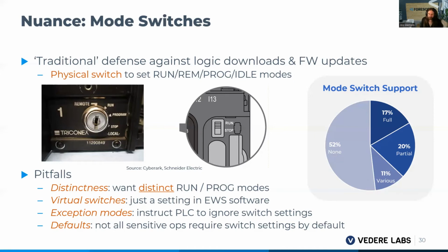Not all mode switches offer the protection you're looking for. There are several pitfalls. First, you want distinct run and program modes that are mutually exclusive: if you're running the logic, you should not be able to do engineering, and if you're able to do engineering, the logic should not be running.